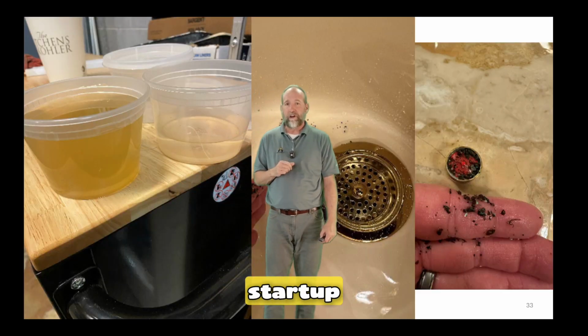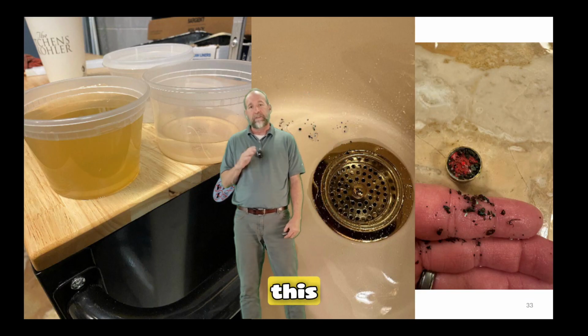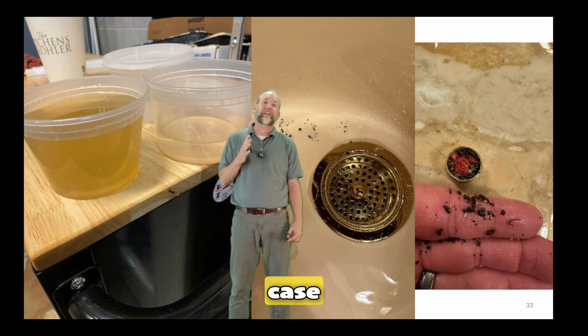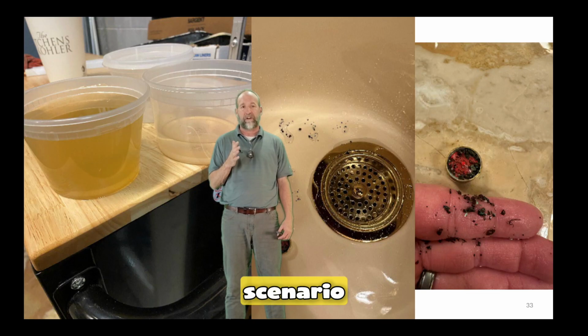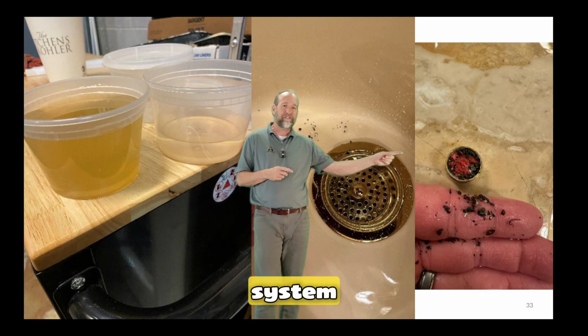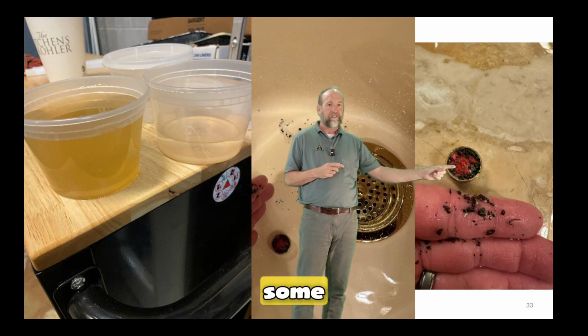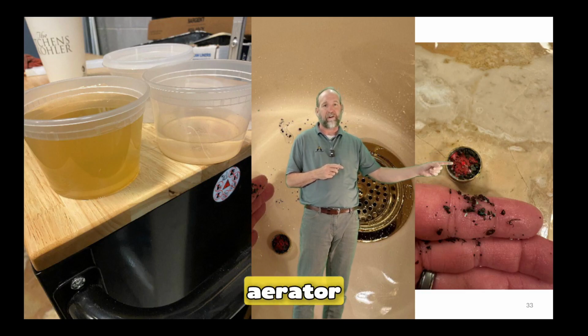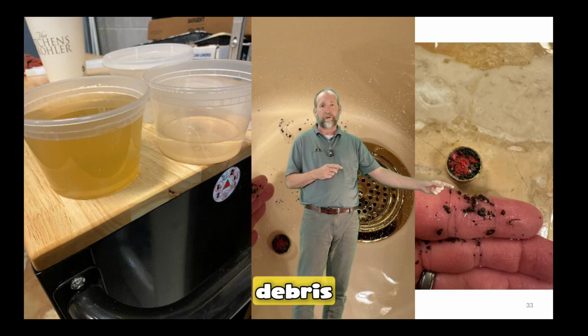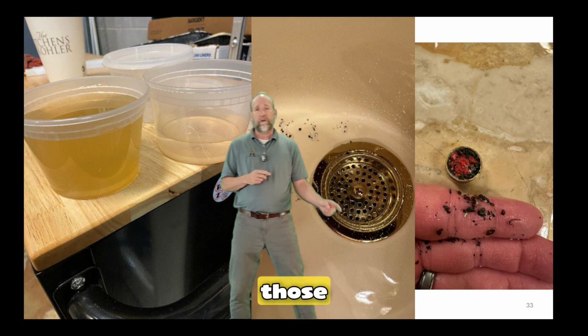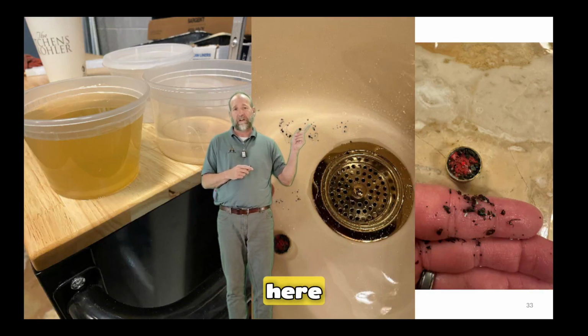So this is a startup on a system right here. And this is what I would say is probably the worst case scenario. I'm going to show you the worst case scenario first. You can see they've got some iron oxide deposits, maybe some biofilm and different things. This is an aerator off of a faucet in a hospitality setup. They got some chunks of scale, some chunks of debris and things like that. Those types of things can end up in the sink here as well.